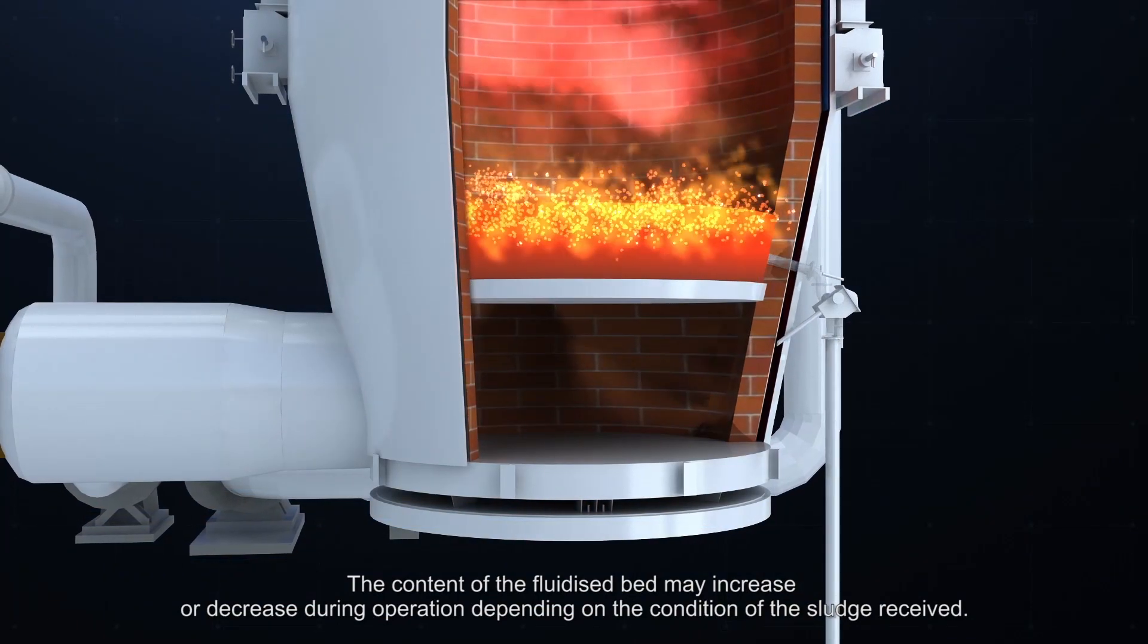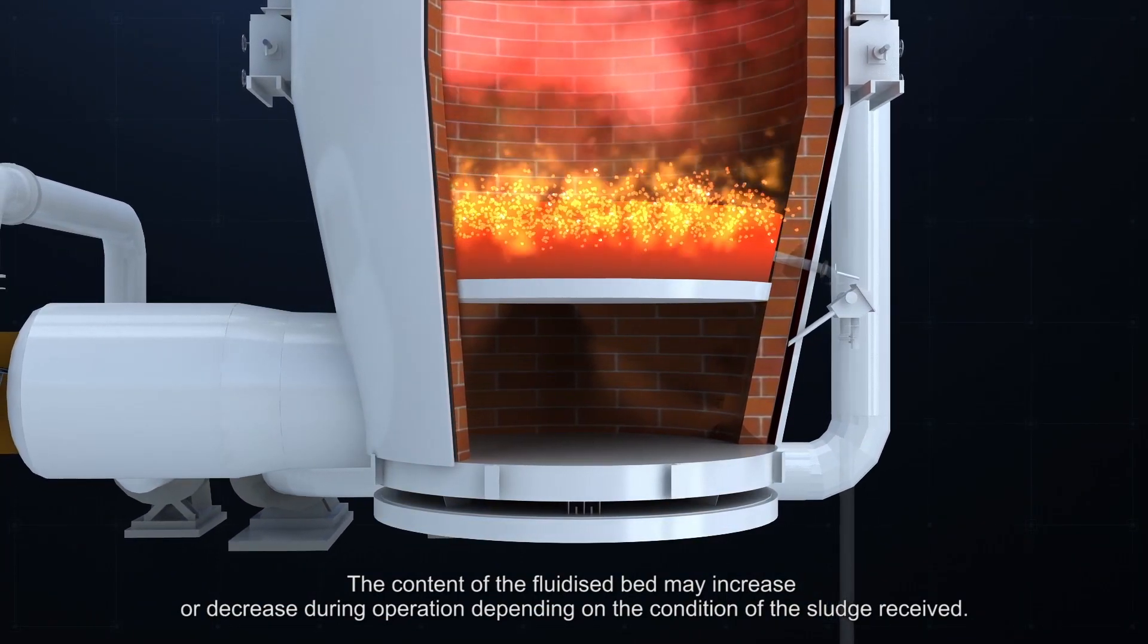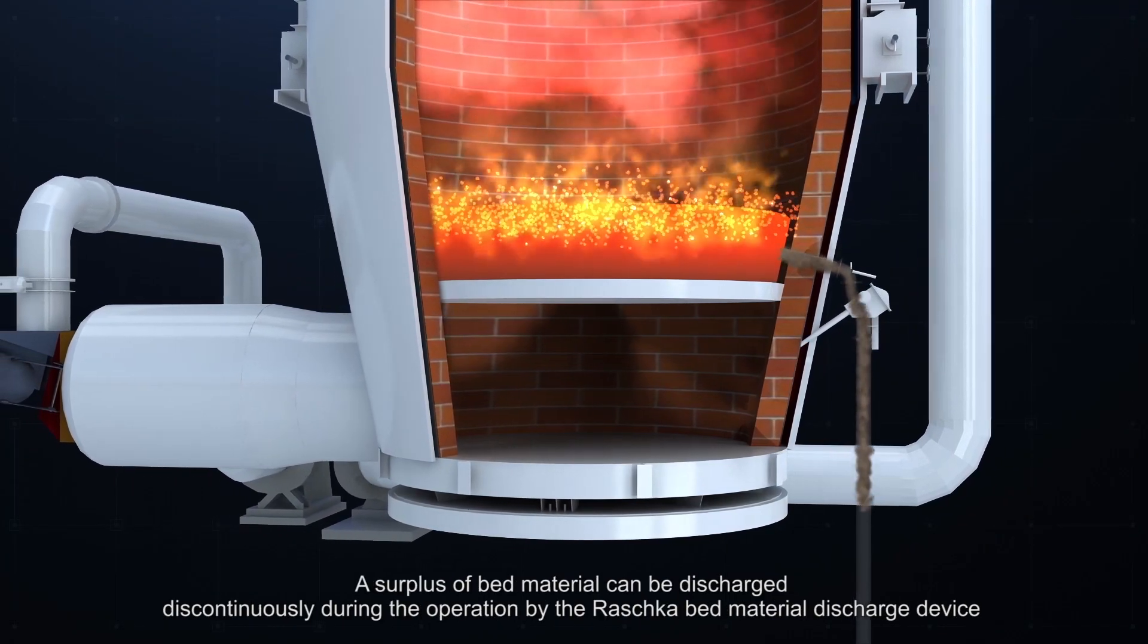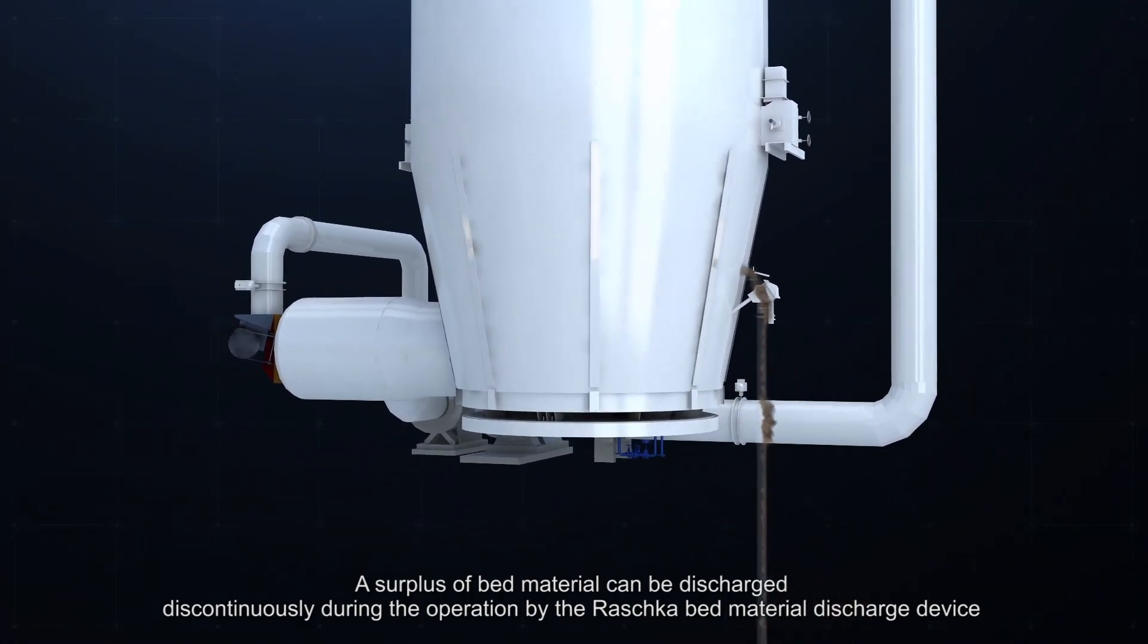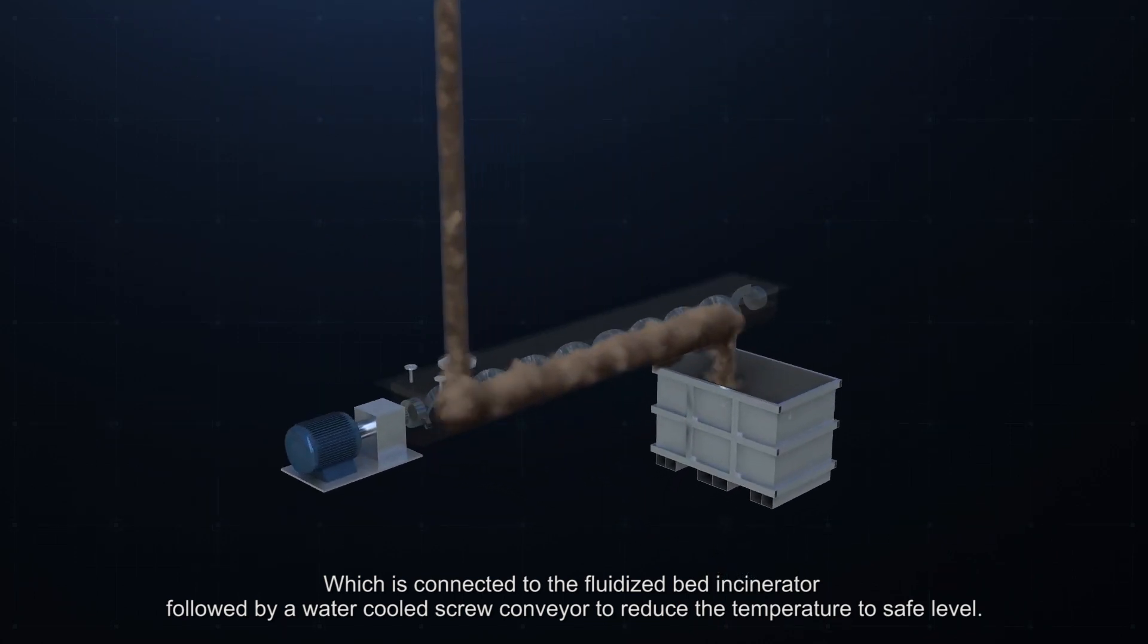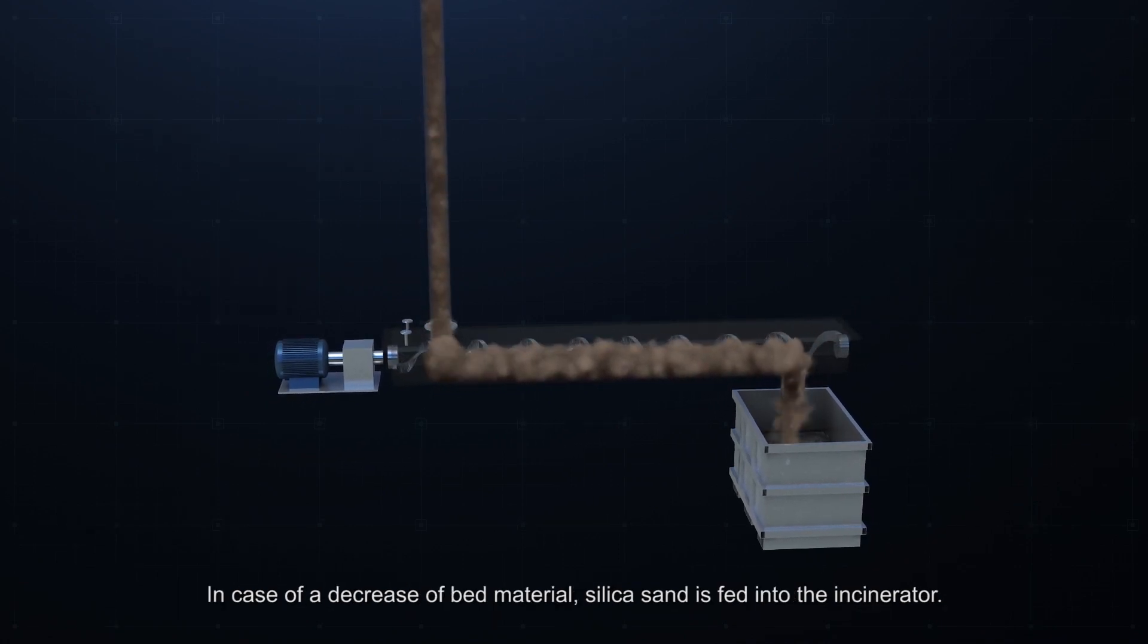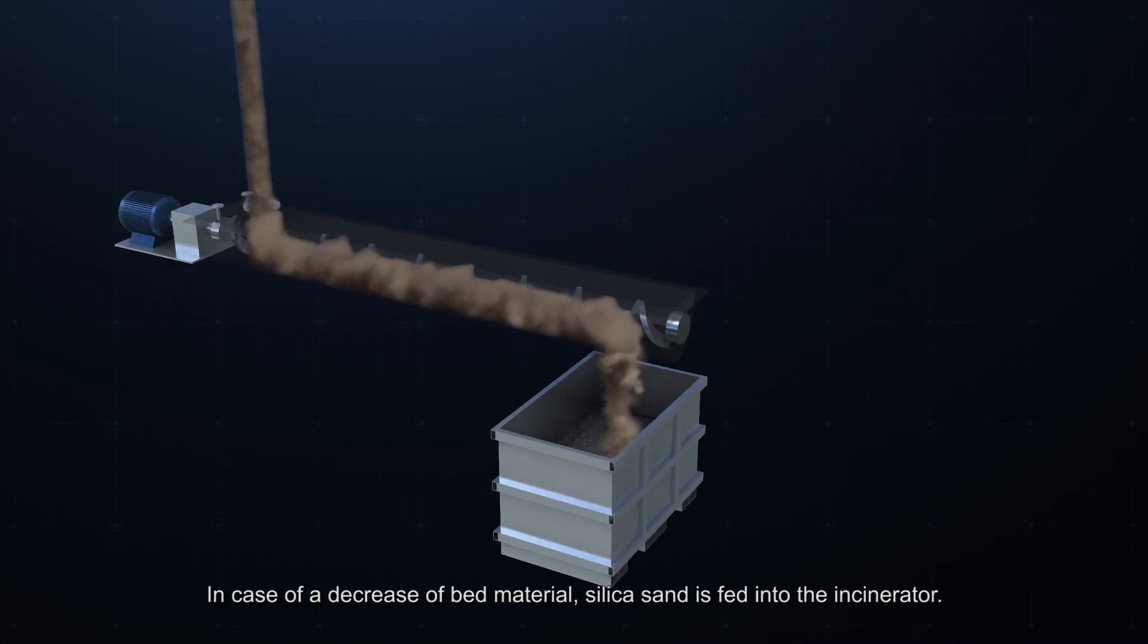The content of the fluidized bed may increase or decrease during operation, depending on the condition of the sludge received. A surplus of bed material can be discharged discontinuously during the operation by the Raschka bed material discharge device, which is connected to the fluidized bed incinerator, followed by a water-cooled screw conveyor to reduce the temperature to safe levels. In case of a decrease of bed material, silica sand is fed into the incinerator.